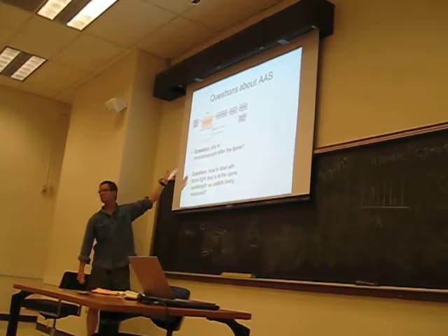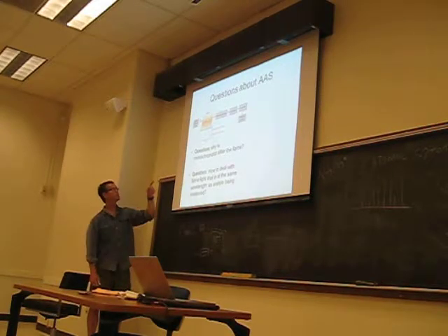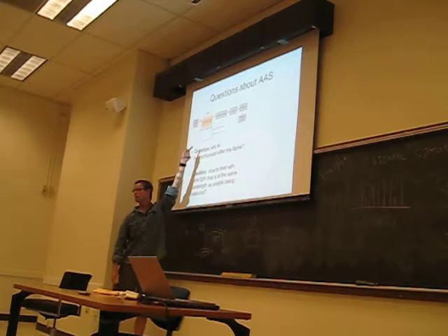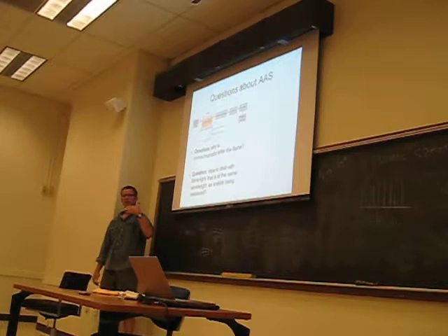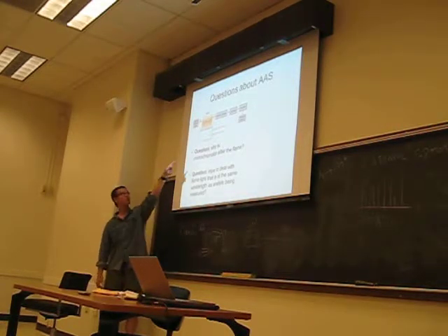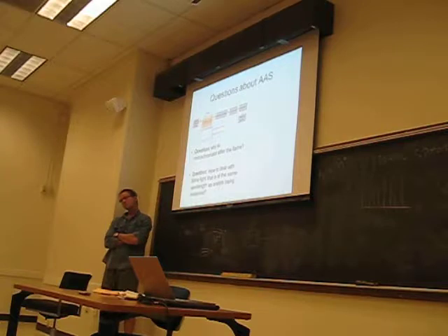So in this case, for flame, and it's this way for a lot of atomic absorption instruments, why is the monochromator here coming after the flame? Your sample is there in the flame. In UV spectroscopy, the monochromator came before the sample cell, right? But here, the monochromator diffraction grating is coming after the flame.